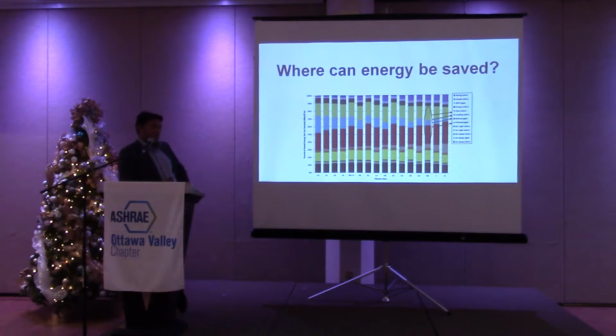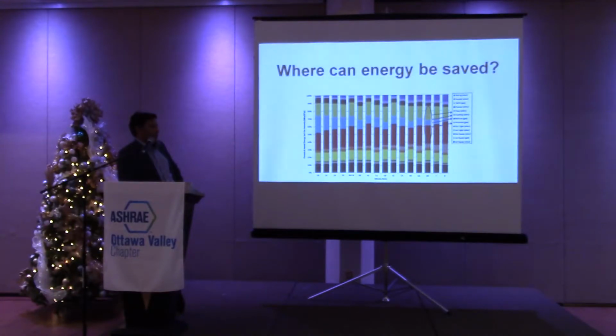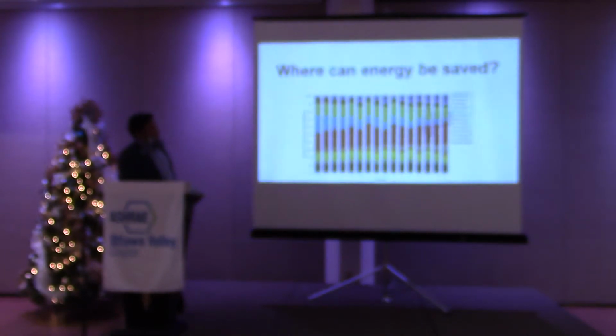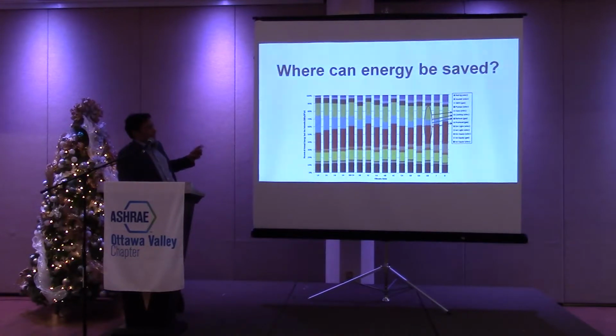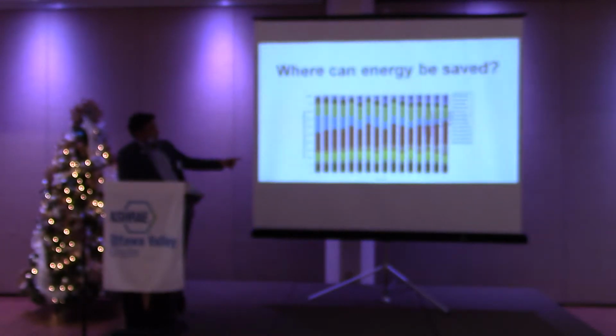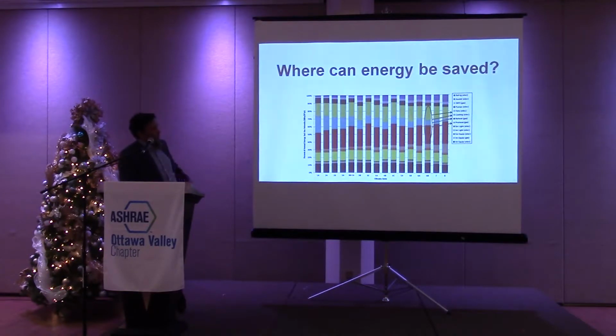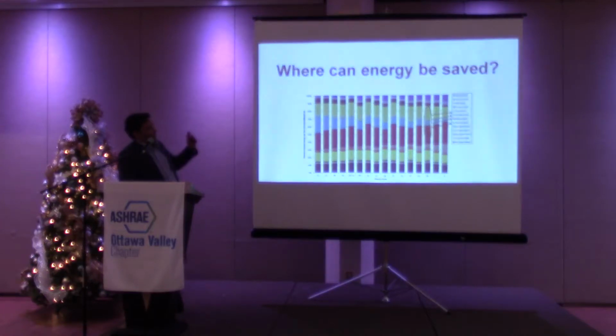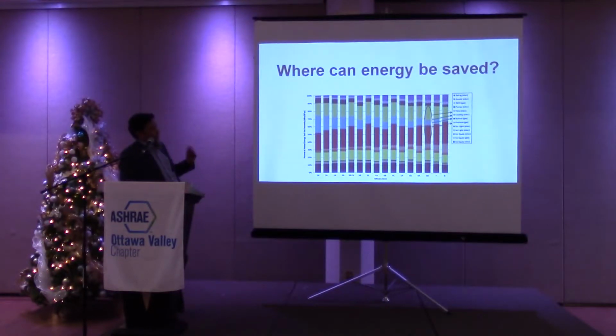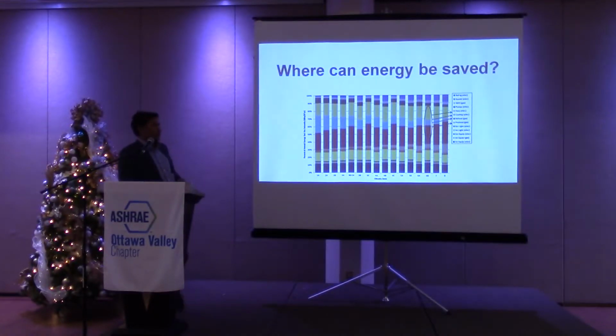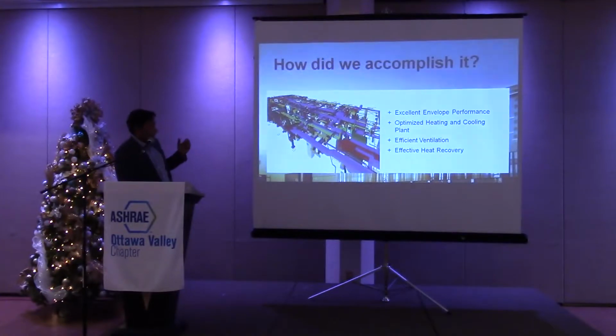So the interesting part, and I guess the focus of today's presentation, really is about energy. So we talked about this aggressive energy target and how we're going to get there. So this is a graph out of the ASHRAE handbook for healthcare facilities. And what these bar graphs represent is the total energy consumption in acute healthcare facilities, and it's for the various regions. So we're in region 6B. And as you can see, the green region up there represents the amount of fan energy consumed in the building, and the red bar graph represents the amount of reheat energy used in the building. So if you're trying to hit these aggressive energy targets, it makes sense to focus on the biggest chunks there and try to reduce the energy consumption. And so, how do we go about that?